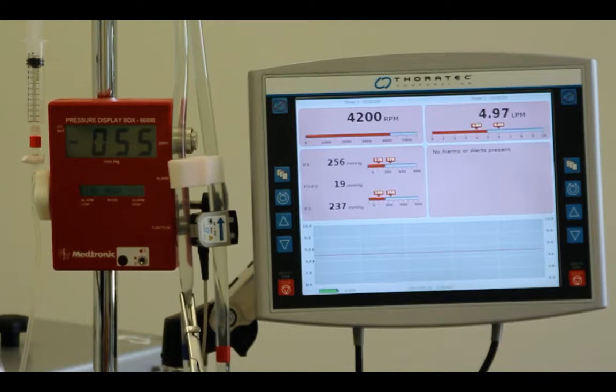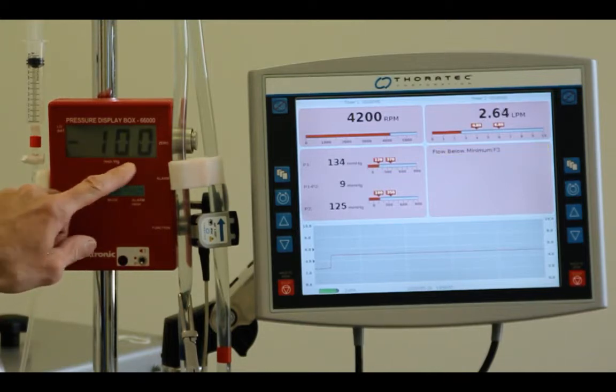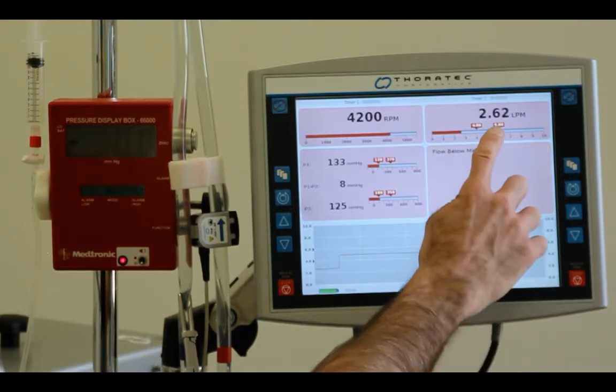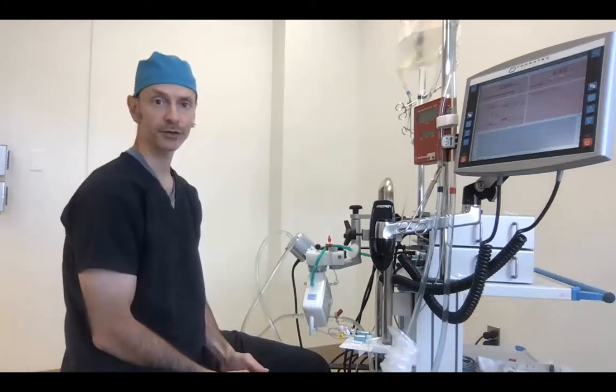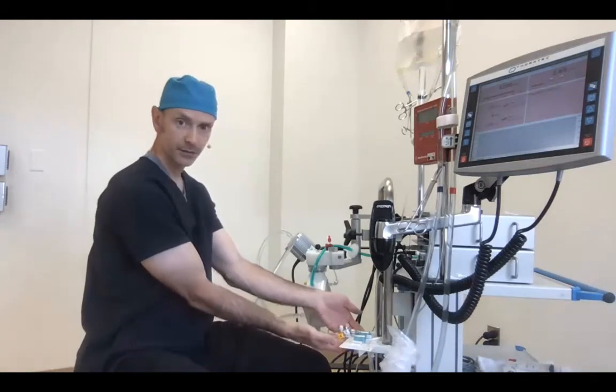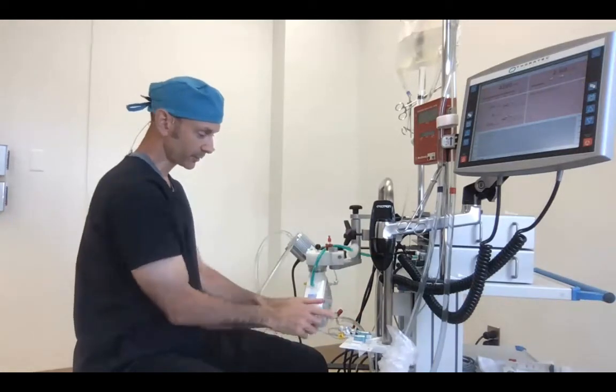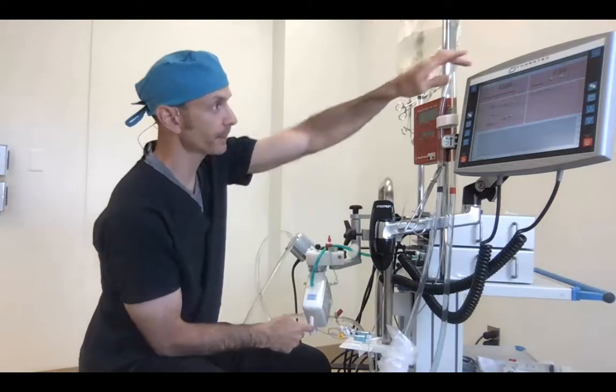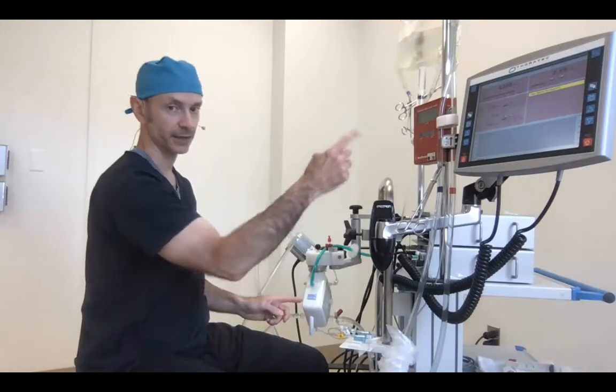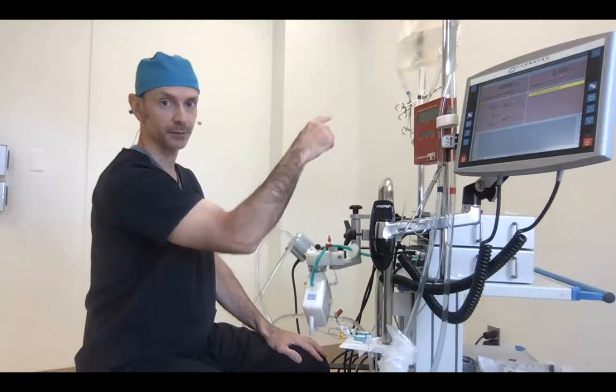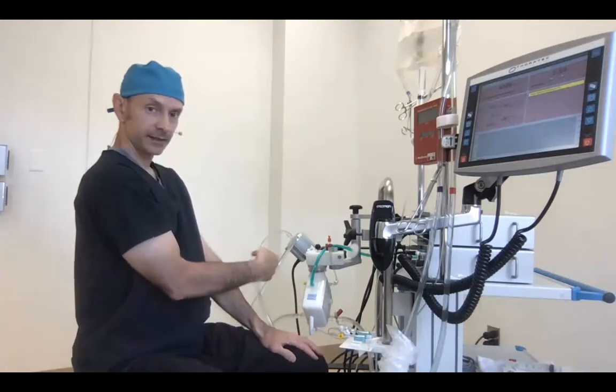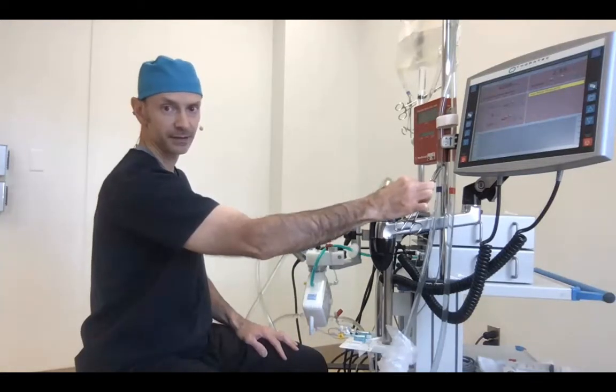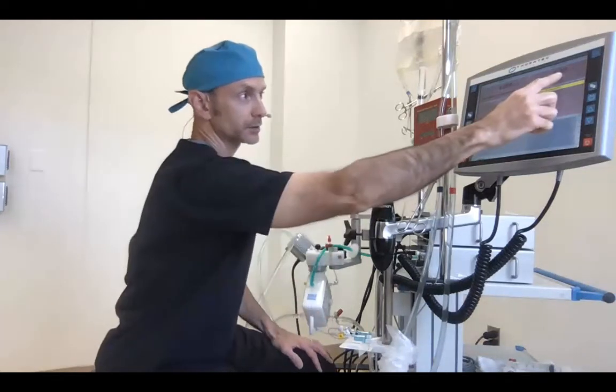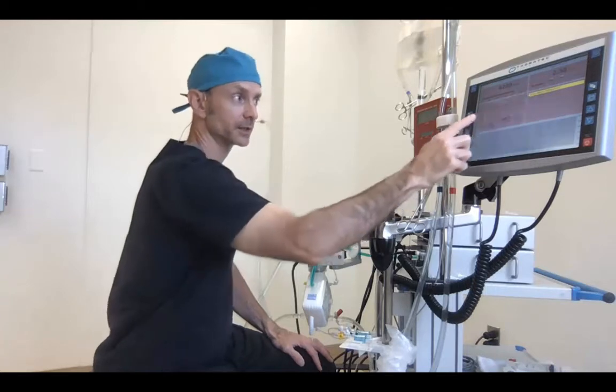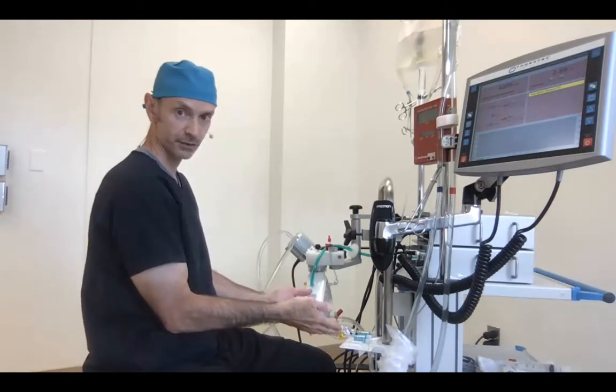Here comes some venous resistance. Give that a moment to update, and we can see that now we're more negative in the venous line. We have lower flows, and we have lower oxygenator pressures, and that makes sense. These pressure sensors over here that are monitoring the oxygenator can't see this clamp. They only look forward. P1 can see the oxygenator, the arterial line, the cannula, and the patient. P2 can see the arterial line, the cannula, and the patient. And they don't know what's behind them. And this clamp is ultimately behind them on the venous line. So all they see is the flow is lower, and pressure equals flow times resistance. If the flow came down, then the pressure comes down, because the resistance, as far as they're concerned, didn't change.